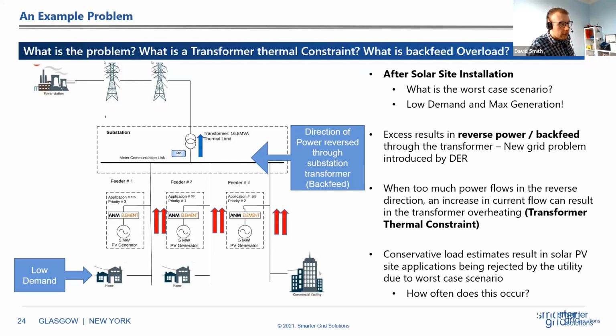And in order to plan for that bidirectional flow, it could be quite expensive, because you're having to buy more expensive transformers, say. And the difficult thing is this doesn't happen very often, but the traditional way of planning these networks is that you plan for the worst case scenario. So you plan for that low load scenario, but high generation scenario.